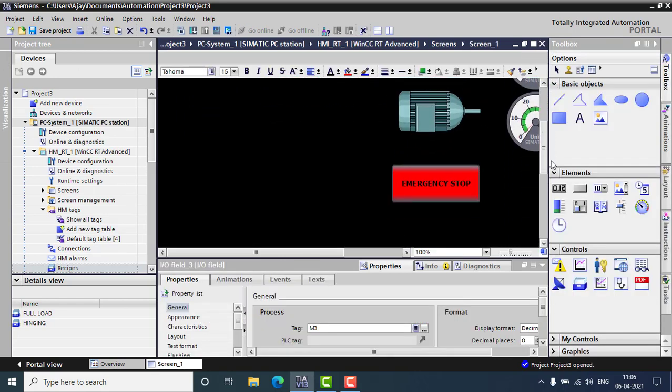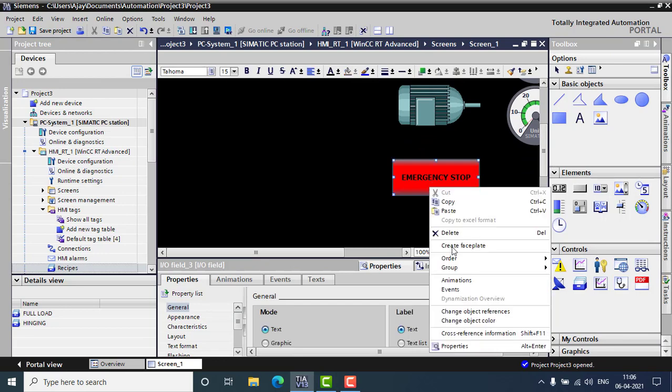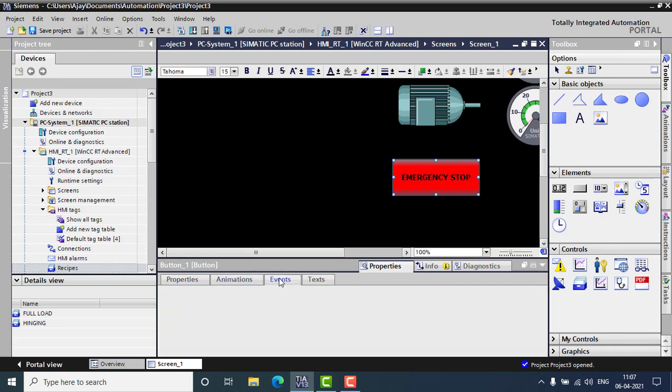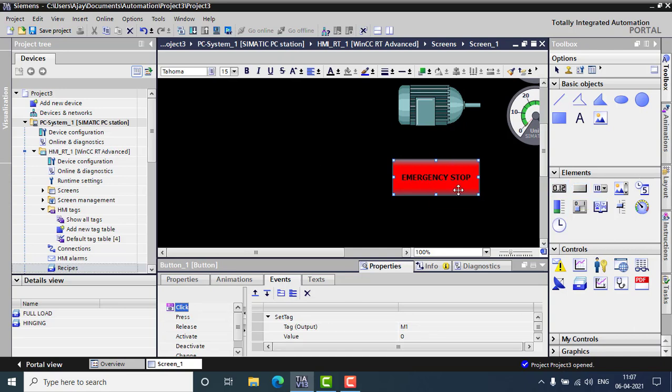And we can set up an emergency stop, which I have already configured. I can show you the properties. Inside the properties, you can go for events. In the events, it's just a button taken from here. I just changed the colors and put the name as emergency stop. And the events, you can see, have to set the tag. On the click, on the events, you can select the click and set the tag as tag value output.